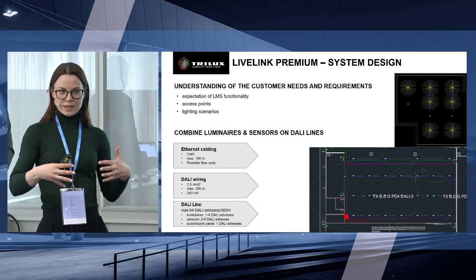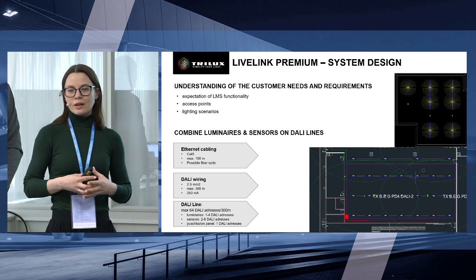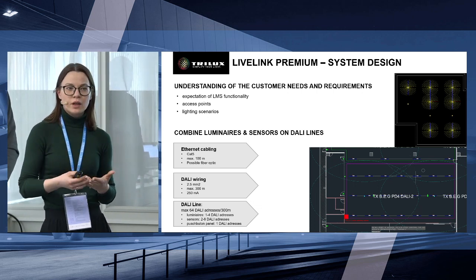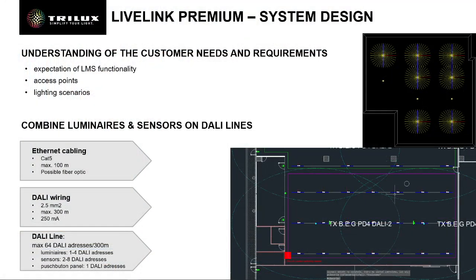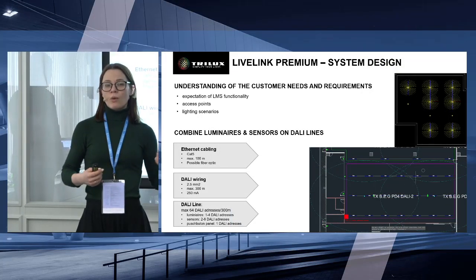Our light management system is based on DALI technology. When preparing our solution, we have to remember DALI's limitations. If we know what our customer wants, if we know if they need sensors, we finish the lighting, we finish the part connected with sensor arrangement. We combine luminaires and sensors on DALI lines. As I said before, DALI has limitations. First of all, we have to remember the distance in Ethernet cabling is maximum 100 meters. The second option is using fiber optic.